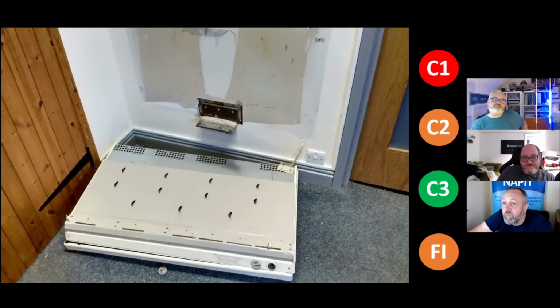Hang on, before we go moving on and say oh no, it's not C1 - where that cable's pulled really tight like that, it didn't lightly just fall onto the deck. That's come down with an almighty bang. What if it's pulled that cable out and now that casing's live? I've not looked at chat, but I'm going to speak on behalf of Phil, and I expect this is his answer. The reason that's going to be a C1 for him is because it puts you in the position where you've got to remove - so you go there, assuming it's on that spur, you disconnect the load. If it was a C2, it wouldn't put you in that position, and that's something Phil does do. He goes, 'I'm going to make it C1 so I've got to do something about this right now.' He kind of does it like that. Yes, it's not live, yes it's not exposed and live, but you want to do something.